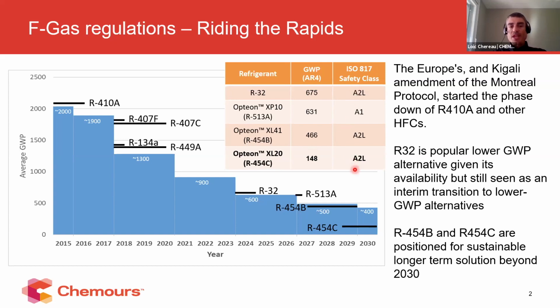The last thing here I wanted to talk about, because this is somehow the trigger for developing and for using these two blends, is the flammability and the behavior these products are having compared to the HFC 410A or 407C that are A1, that are non-flammable. These two blends are mildly flammable, which means that there are some risk assessments to be considered when the OEMs are using these refrigerants. So there are different factors and means to mitigate the risk, depending on, again, the refrigerant that is used, to make sure that they are applicable.